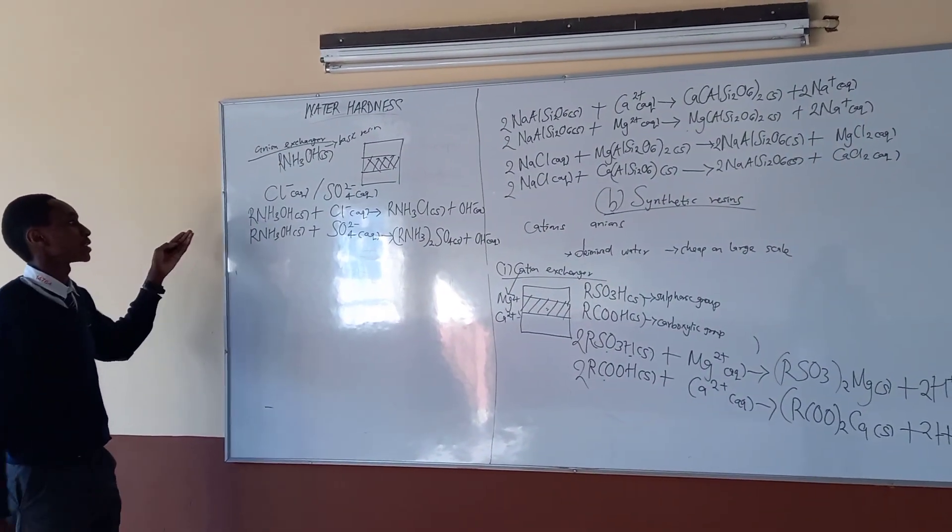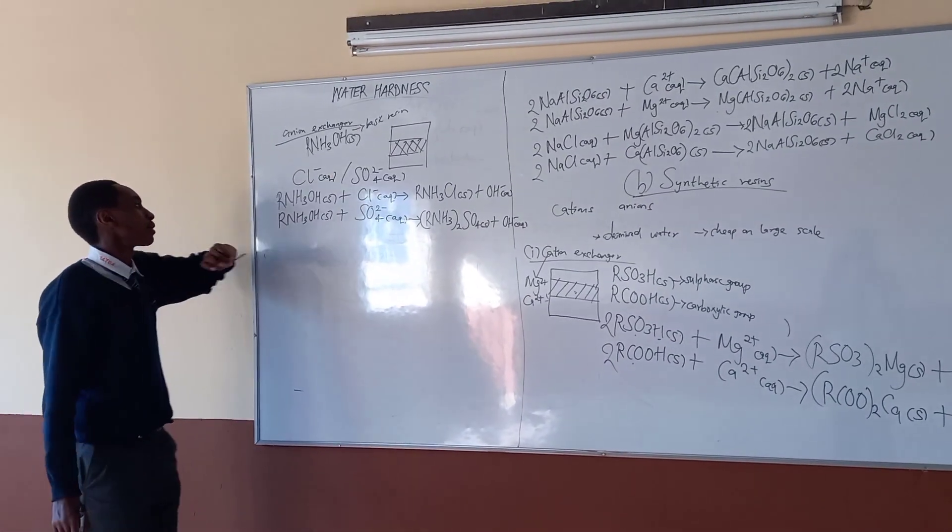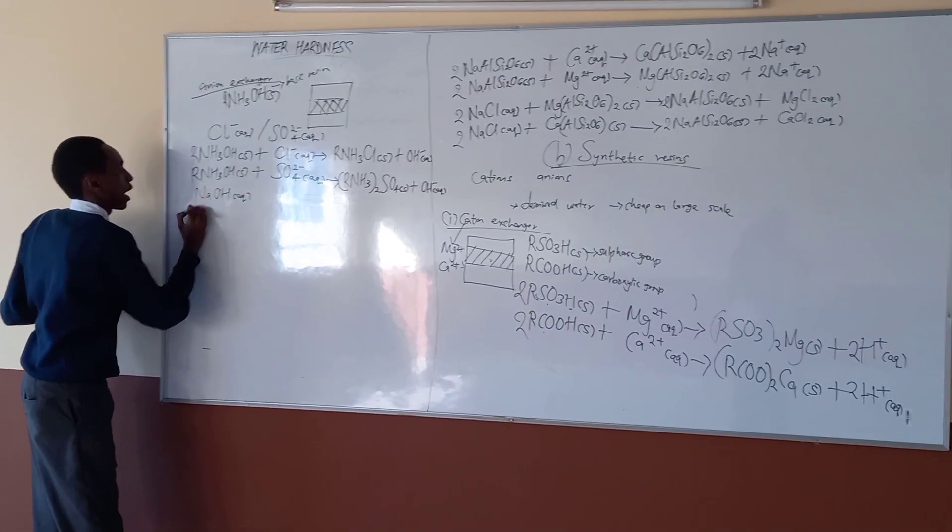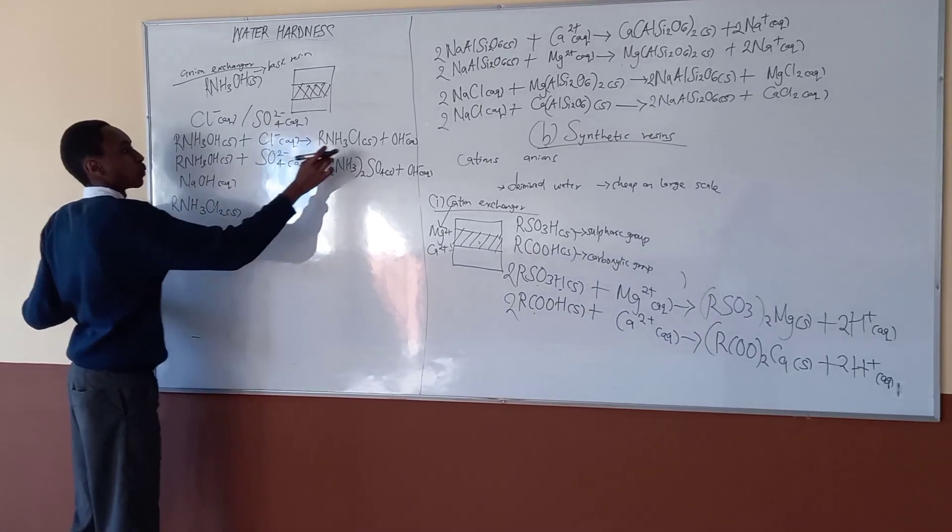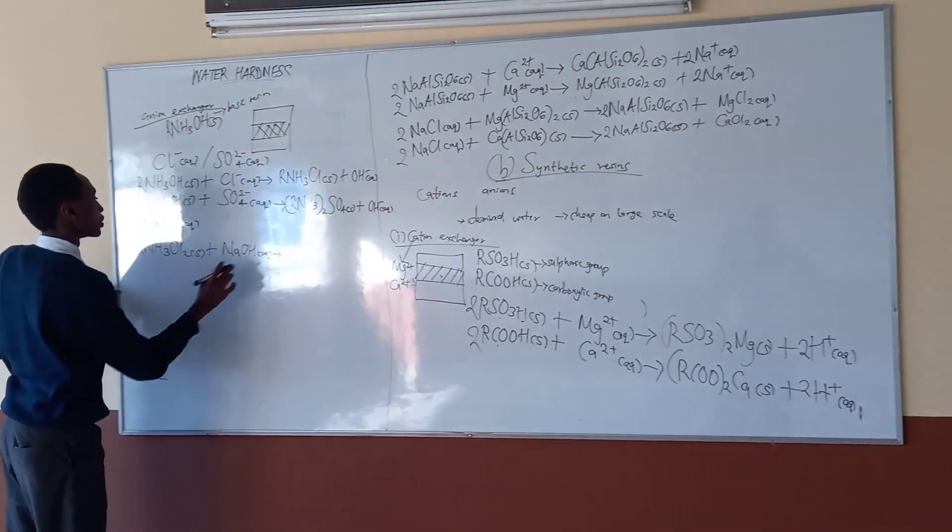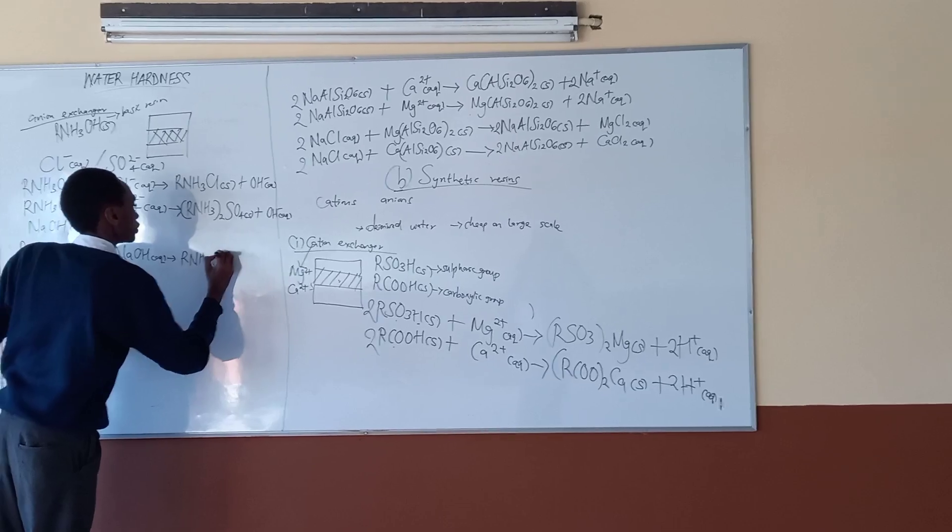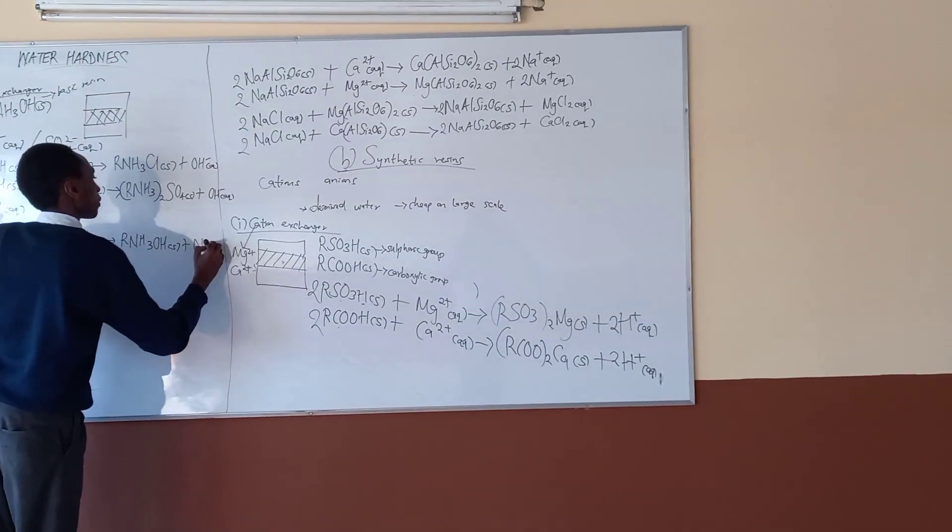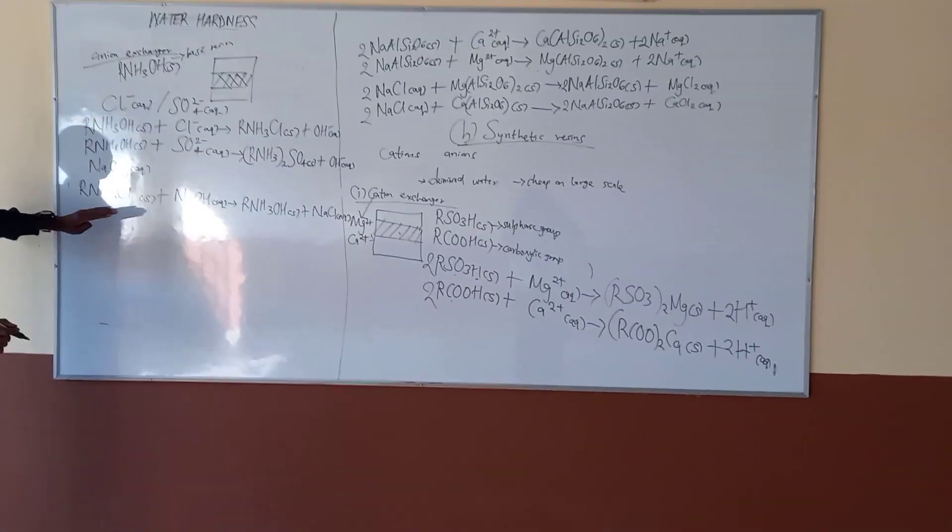Over time, obviously, we get to use up the basic resin. What we do is we flush this chamber, the tank, using sodium hydroxide aqueous. So, RNH3Cl solid, we want to remove this from the tank, plus sodium hydroxide aqueous. So we get to restore the hydroxide to the basic resin. So it becomes RNH3OH solid plus sodium chloride aqueous. And that is how we have removed the chlorides from the basic resin.